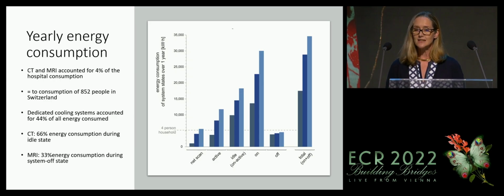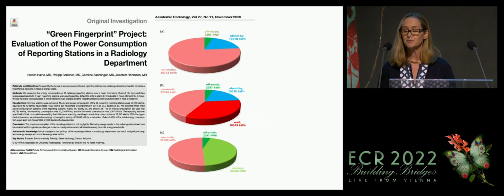They found that the dedicated cooling systems accounted for 44% of all energy consumed. And in CT, 66% of the energy consumption was during the idle state, and in MRI, 33% of the energy consumption was during the system off state. And I've given some histograms demonstrating the energy usage during the scan, during the active, during an idle period, and during the off period. And we can see that there are substantial gains to be had despite not impacting on patient care.